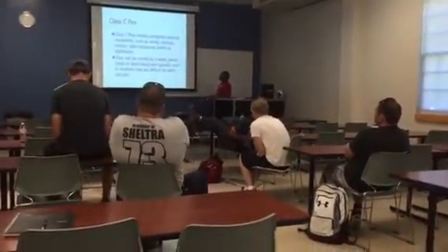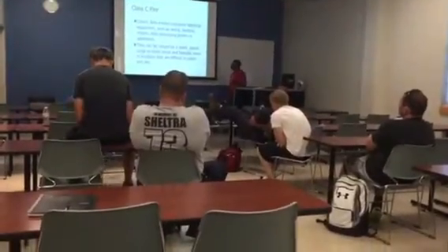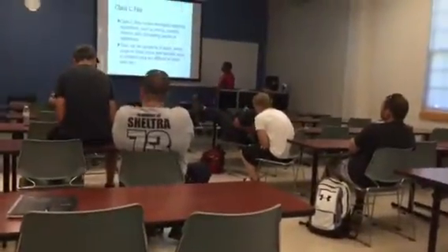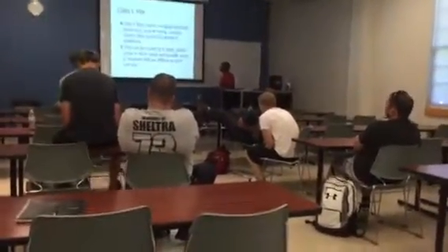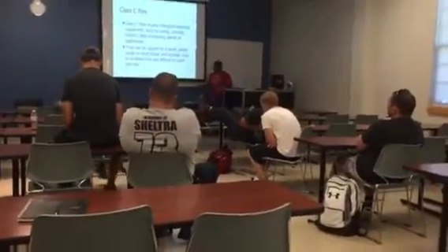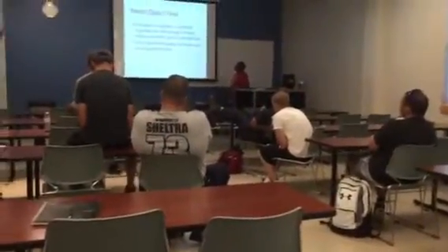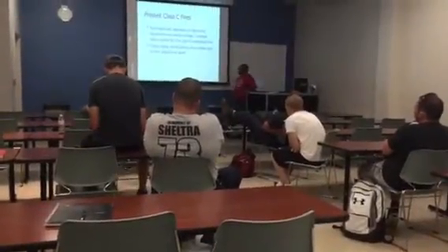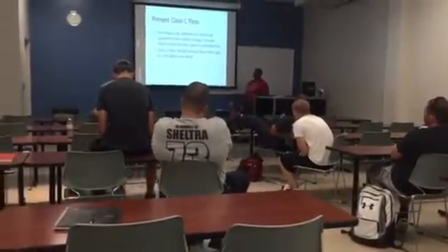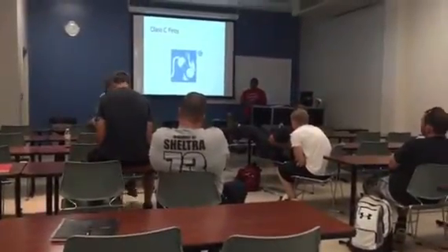Class C fires involve energized electrical equipment such as wiring, controls, motors, and data processing panels or appliances. They can be caused by a spark, power surge, or short circuit, and typically occur in locations that are difficult to reach and see. To prevent Class C fires, investigate any appliances or electrical equipment that smell strange. Unusual odors can be the first sign of a potential fire. Class C fires are represented by a blue circle.